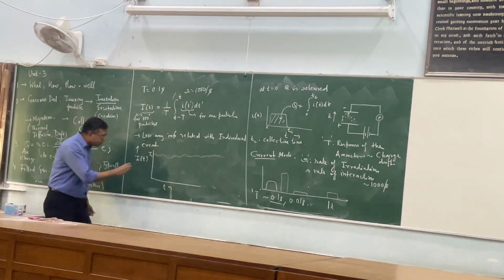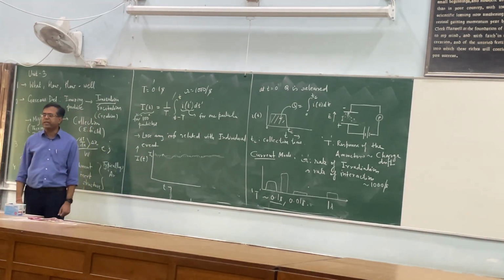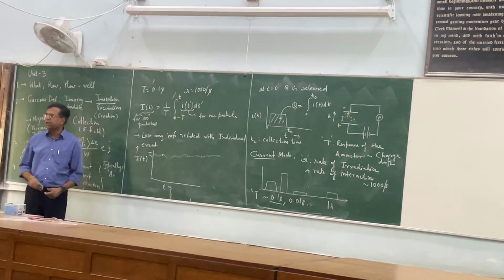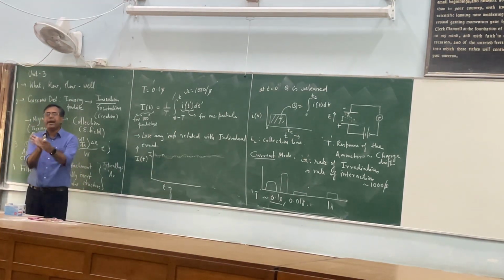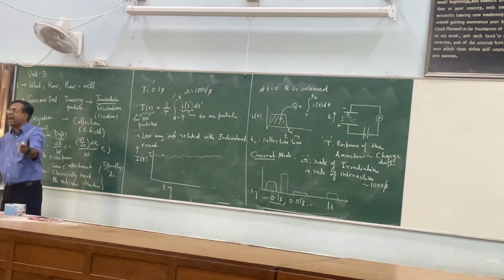But the actual instantaneous current will have some variation with respect to the average, because every time you are seeing 100, not all those 100 have given you exactly the same charge. Because of the statistical fluctuation, each of these 100-averagings will give some variation with respect to the average.